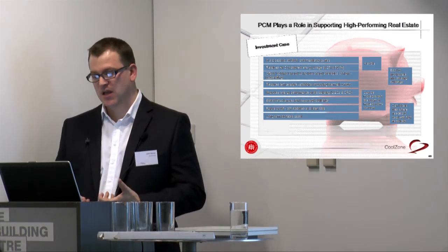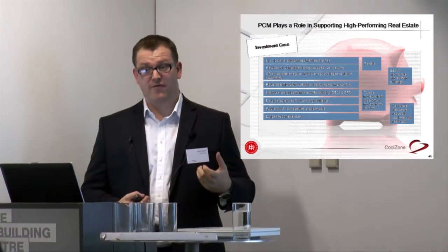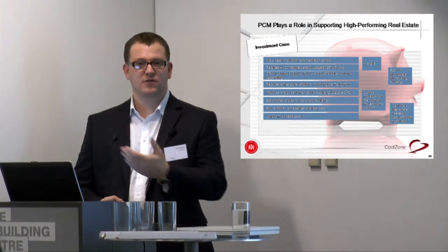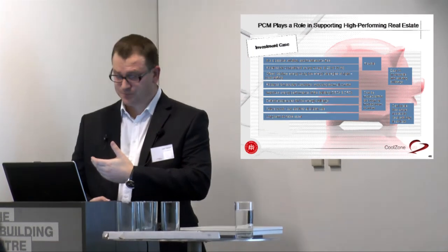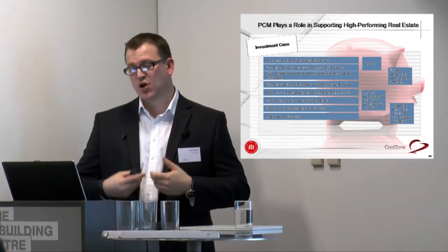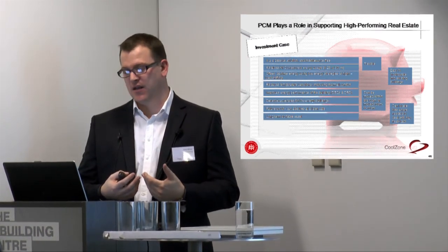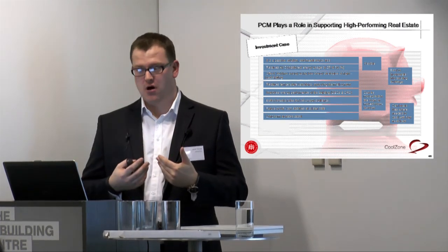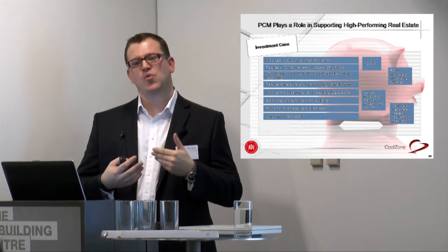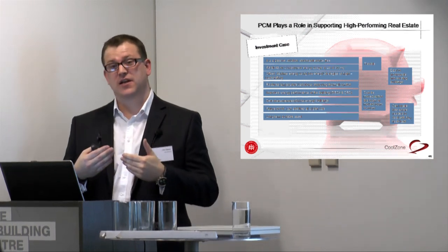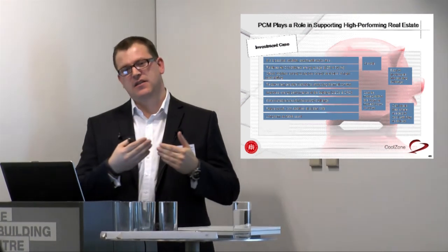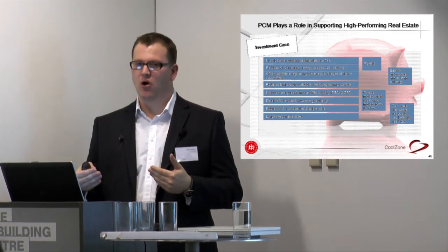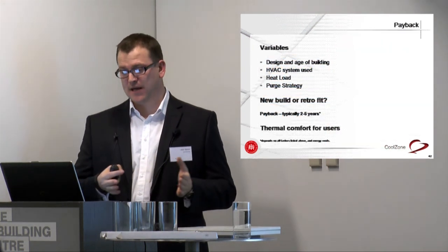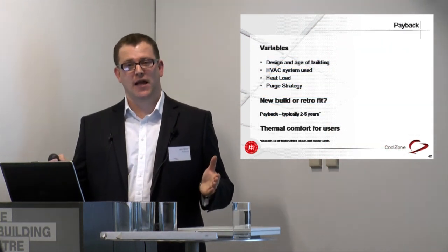What we found was if we have a very low temperature of air, like the outside air we have this evening, we can bring that into the space and purge the tiles very quickly, in this case within an hour and a half. Where we have slightly warmer air, or a slightly slower flow rate, that purge time takes a bit longer, but typically we've got the whole night to play with.